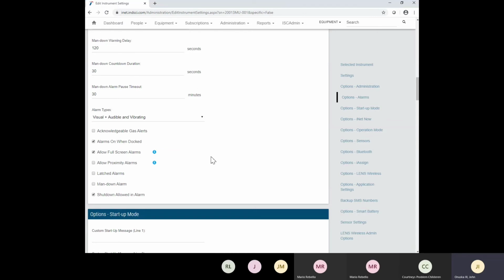If you actually uncheck that, it will do a silent bump test on the docking station. It still tests the speaker. It does it by doing a circuit test on it, but it does not actually enunciate the alarm. So it allows it to do a silent bump test.